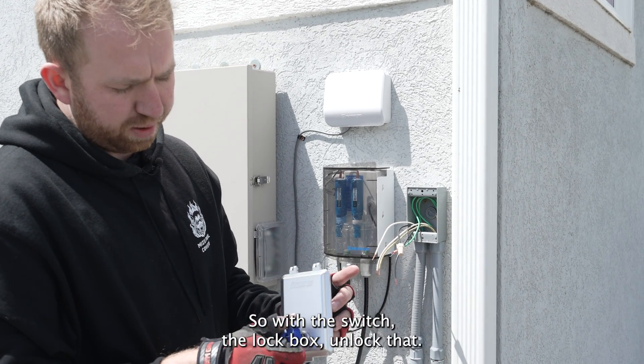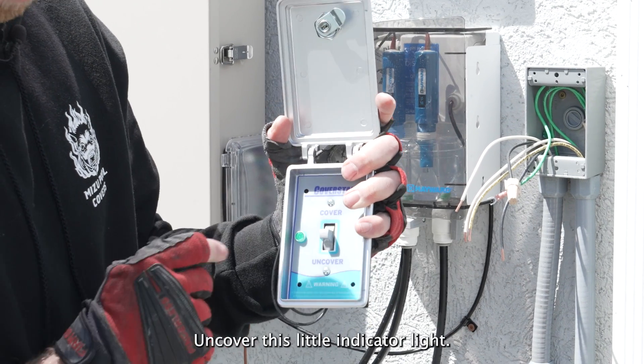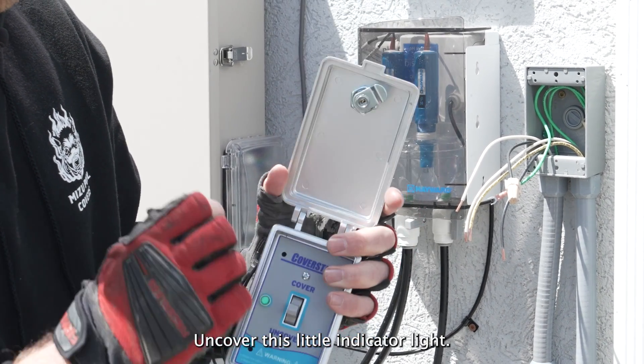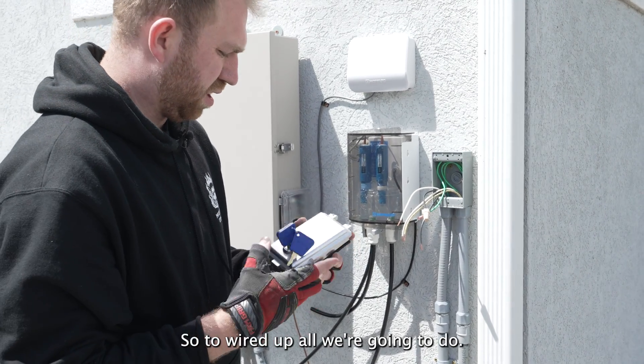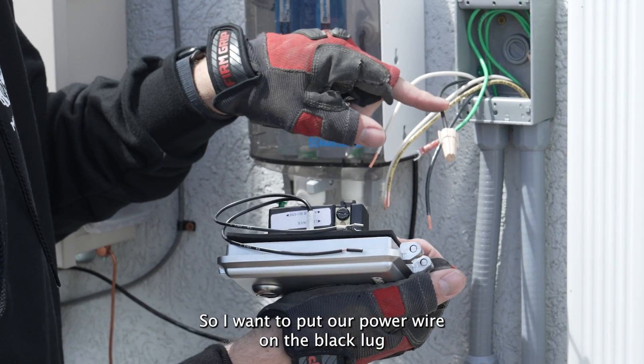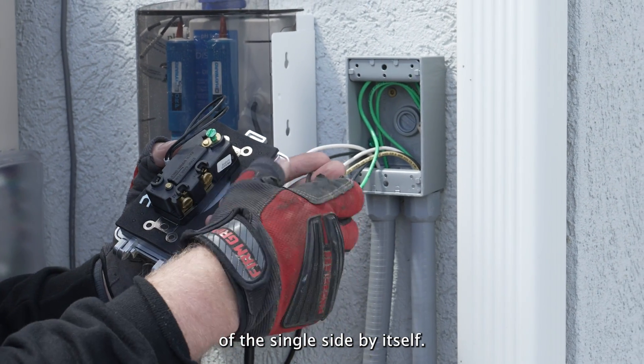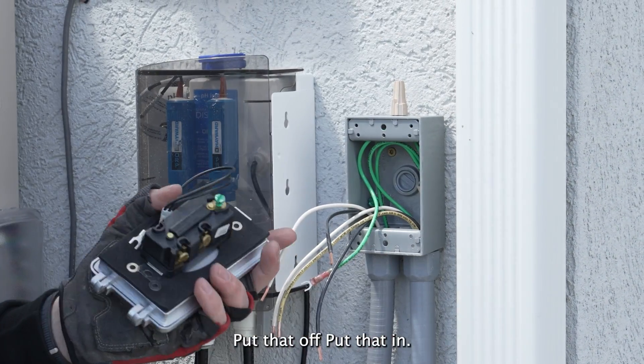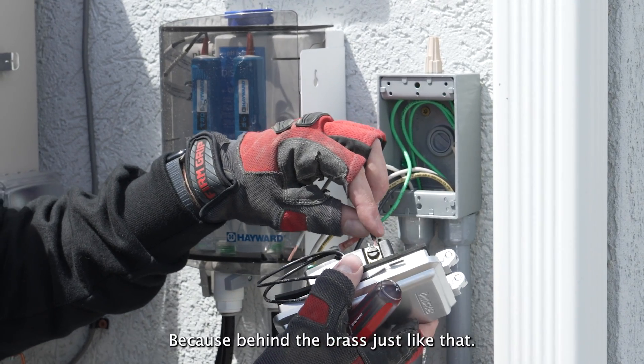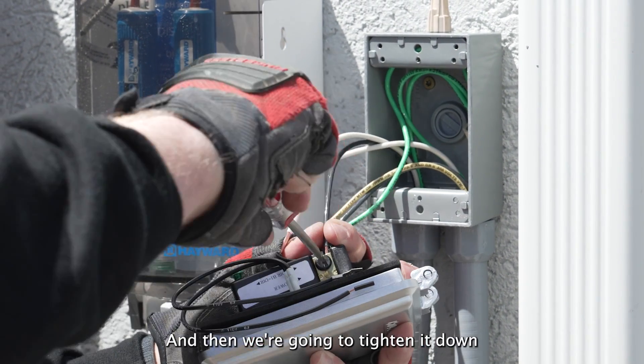So with the switch, the lock box — unlock that. You have your cover, uncover. This little indicator light. So to wire it up, super simple — we're going to put our power wire on the black lug of the single side by itself. Put that in — it goes behind the brass, just like that — and then we're going to tighten it down.